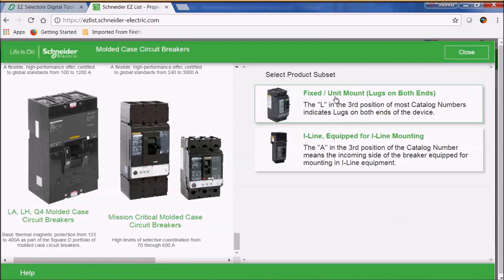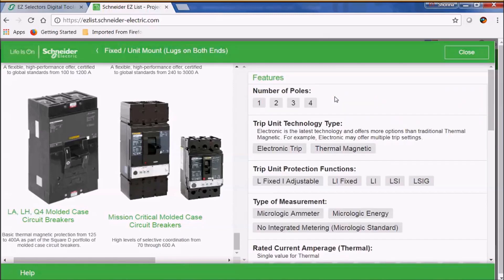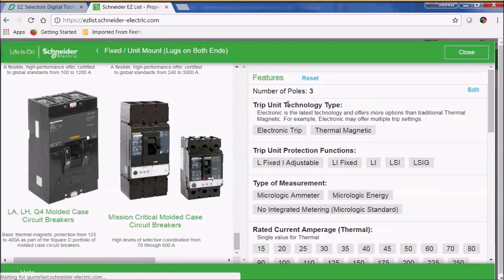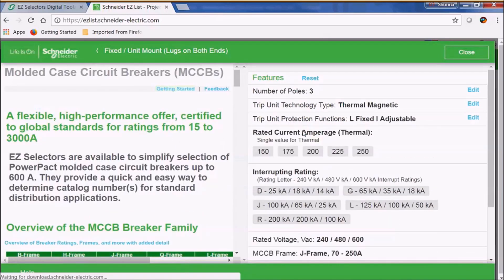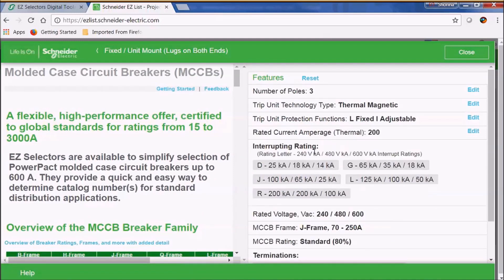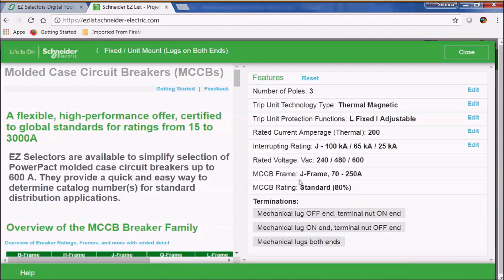Let's go ahead and select a fixed mounted lugs on both ends circuit breaker today. We're going to select a 3-pole, a thermal magnetic, we're going to do the fixed adjustable, and we're going to go ahead and select a 200 amp device. Let's go ahead and select the J rating so that we can get a 65k AIC rating at 480 volts.